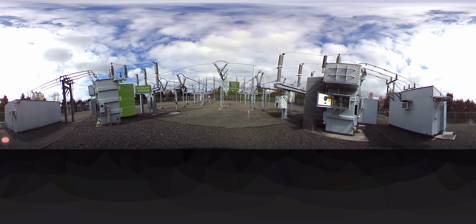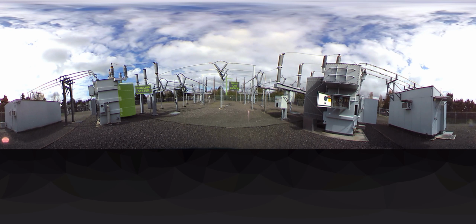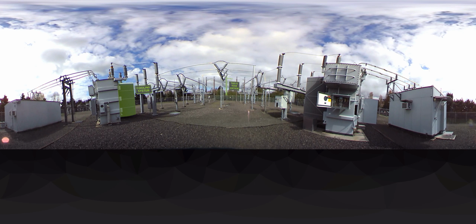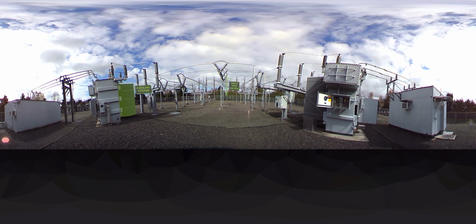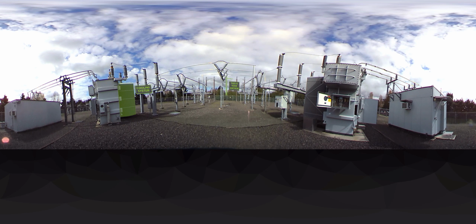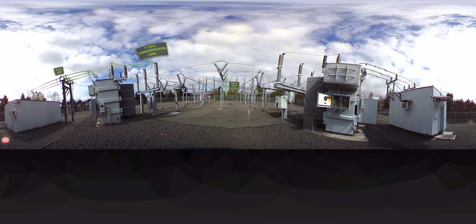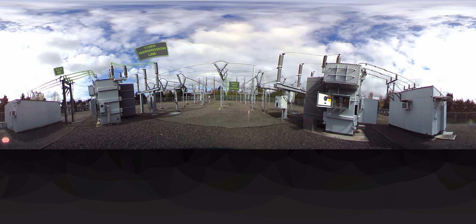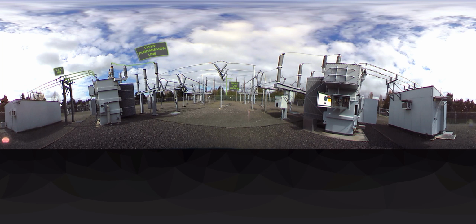This step-down transformer is made from 2 or more coils of insulated wire wound around a core made of iron. When voltage is applied to one coil, frequently called the primary or input, it magnetizes the iron core, which induces a voltage in the other coil, frequently called the secondary or output. The turns ratio of the two sets of windings determine the amount of voltage transformation. You can see the lines clearly going from the circuit switcher or breaker to the transformer. Once again, before entering the transformer, the voltage is 115 kV, and upon leaving, it's just 12.5 kV.